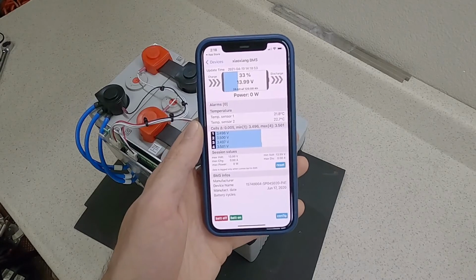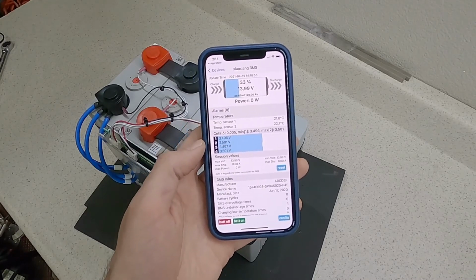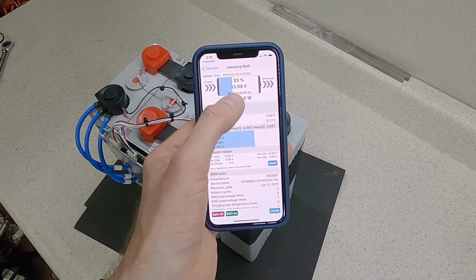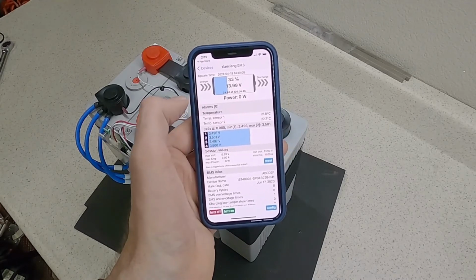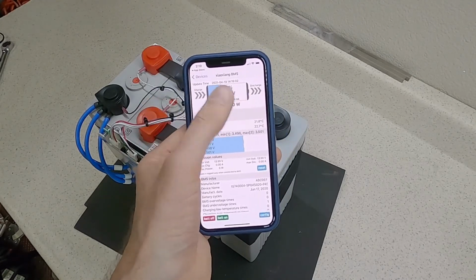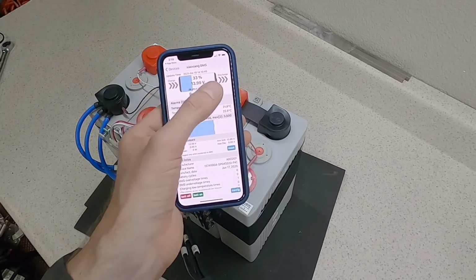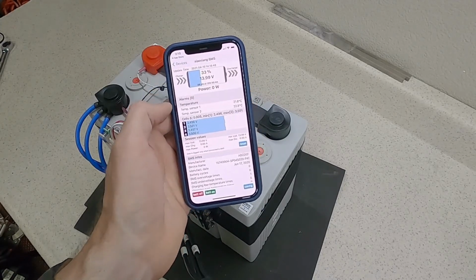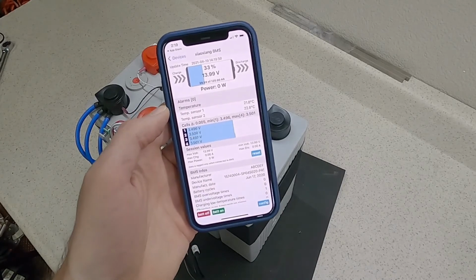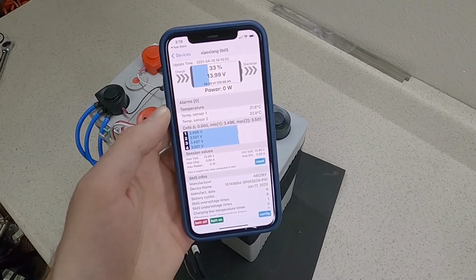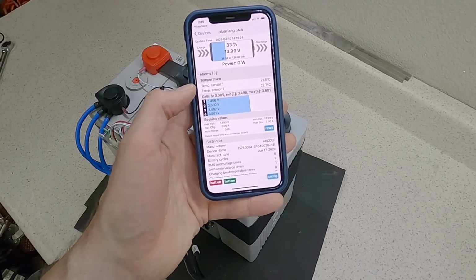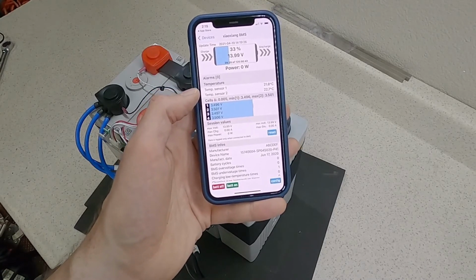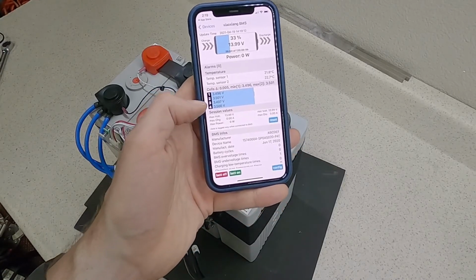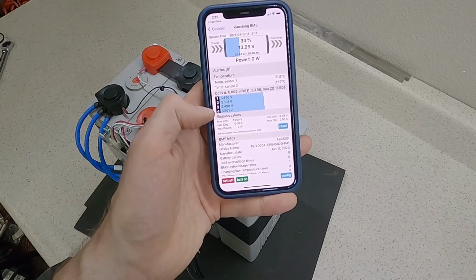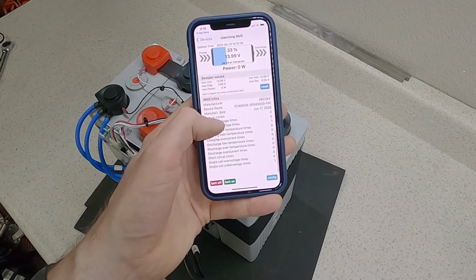If we tap on that battery, it'll load the data and show some cool stuff. At the top we see details like pack voltage of 13.99 volts and percentage of charge, plus whether it's charging or discharging and how much power is going in or out. The percentage is wrong right now because the BMS has factory config settings that aren't right for our batteries, but we'll fix that. We can also see cell temperature, BMS temperature, and individual cell voltages down to the thousandth of a volt.